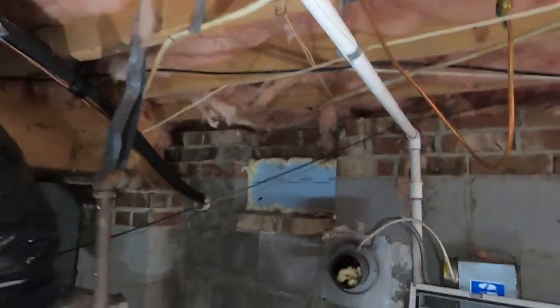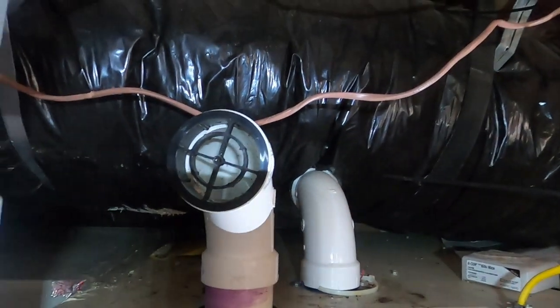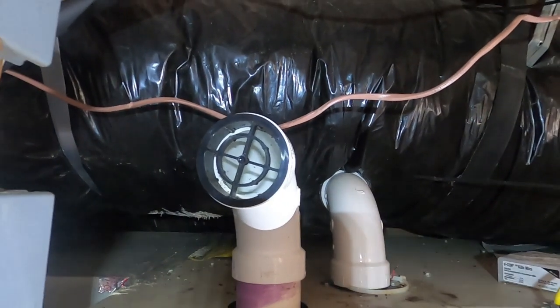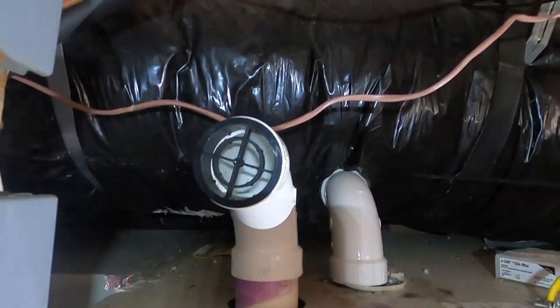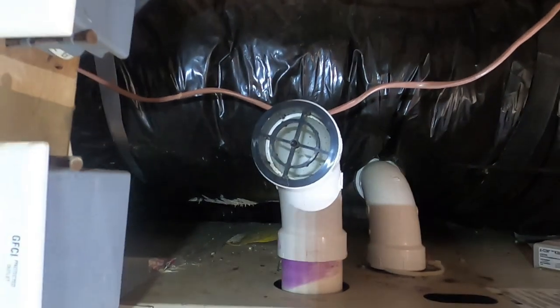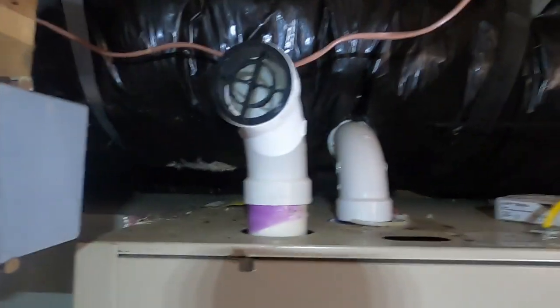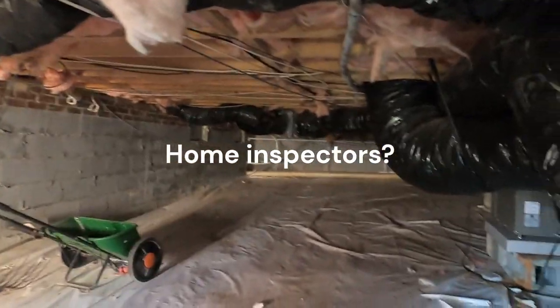We have a sealed crawl space, as you can see. So our combustion air is going to be a problem here. She bought the house, found it this way. She didn't have the unit installed. This was all here when she bought the house. But every register is sealed. The door for the crawl space is sealed with weather stripping, and so that's going to be an issue.